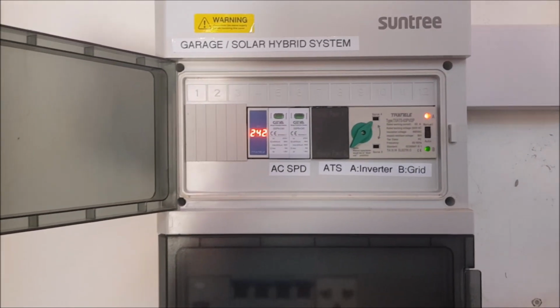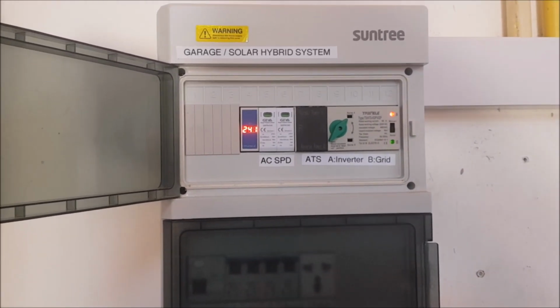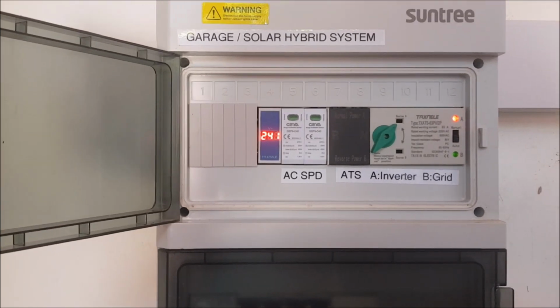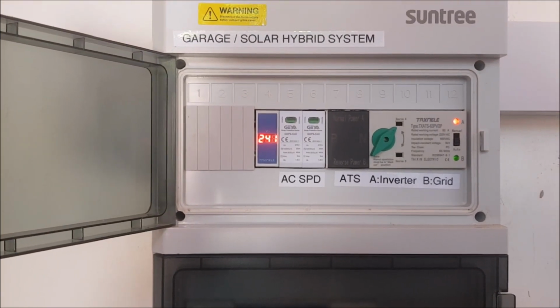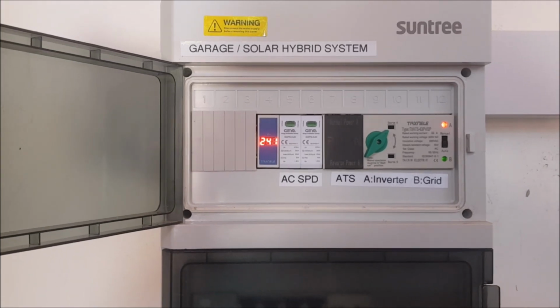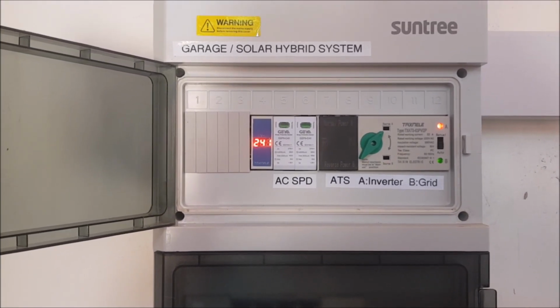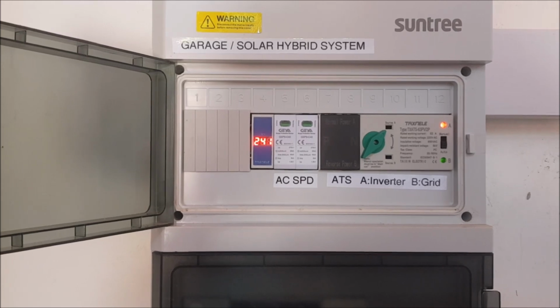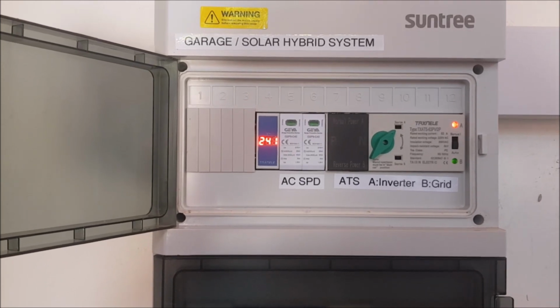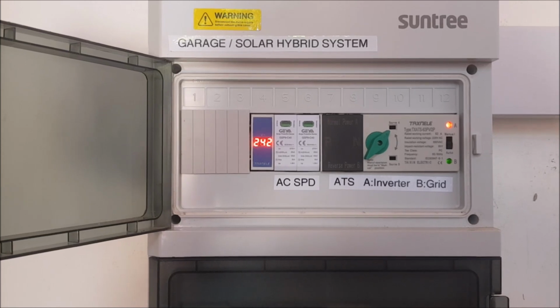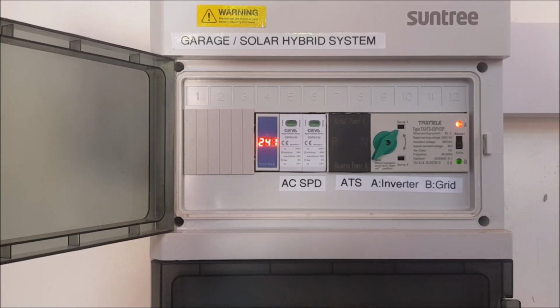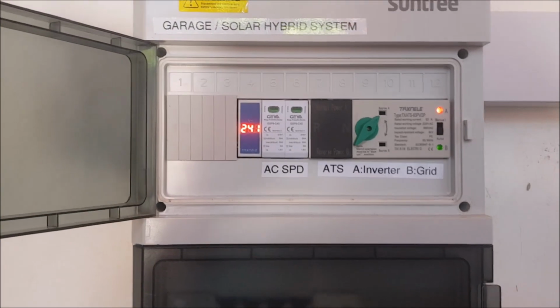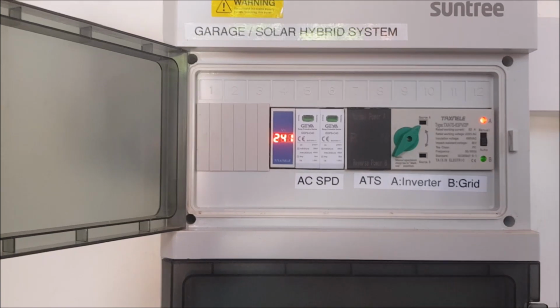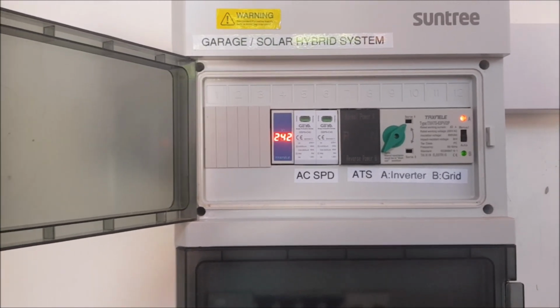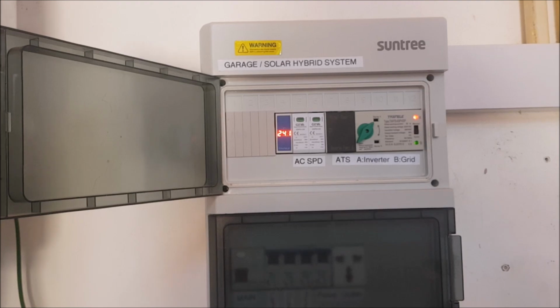But there's a problem here in Thailand, and that's the Thai grid standard. Unlike in Europe, where standards allow 10% deviation from the nominal value, the Thai standard only allows 5%. So 230 plus 5% is 241.5 volts. At 242, which we just saw, the voltage is actually too high here in Thailand.